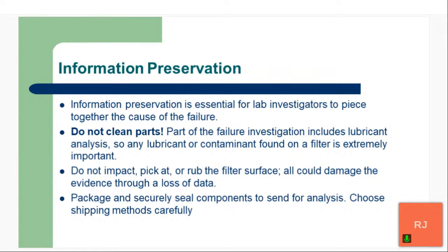The third one's a very important one. We don't want to impact, pick at, or rub the filter surface. We mentioned this earlier. If you do damage the filter while you're removing it due to the situation, you would want to note that for the laboratory so they understand, because otherwise it could be taken as an issue that the filter was going through, and then the laboratory is looking at something that didn't actually happen.